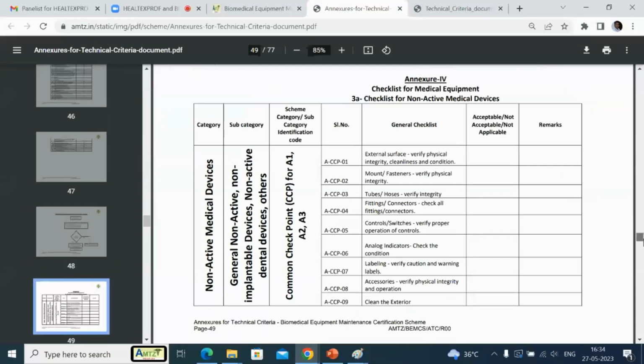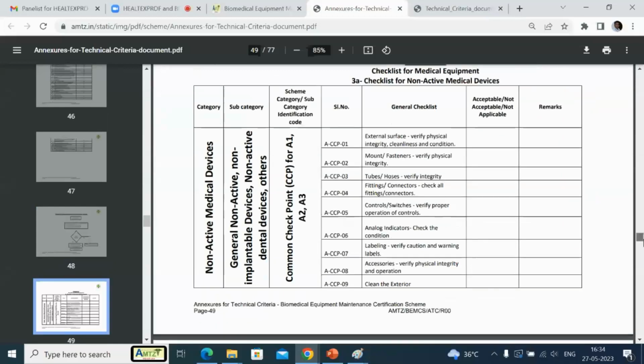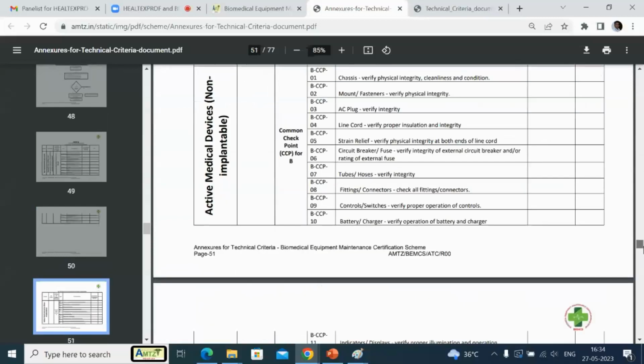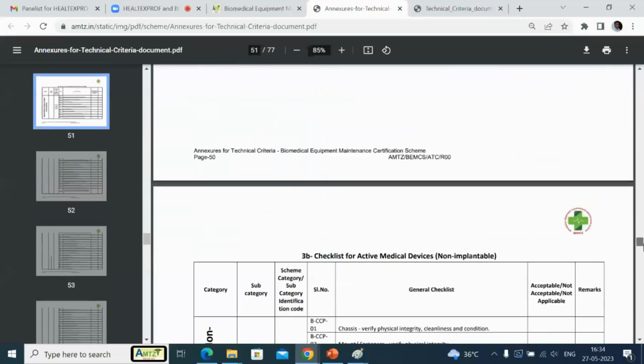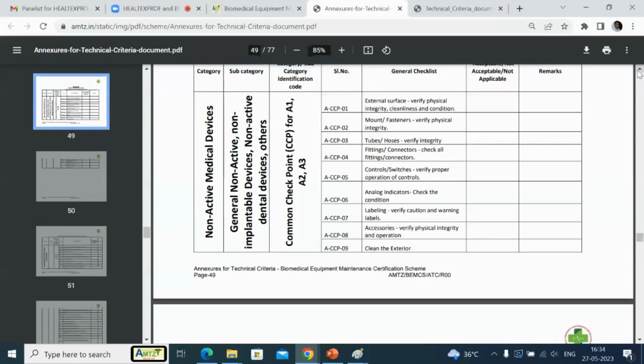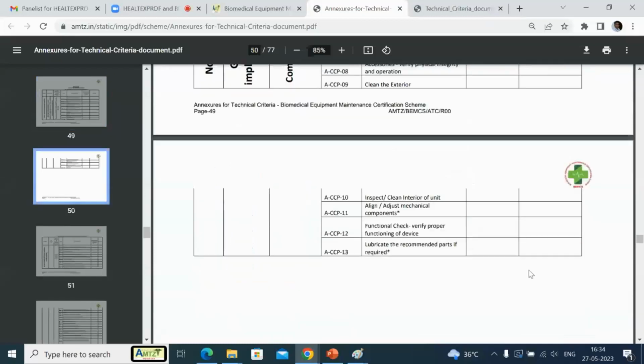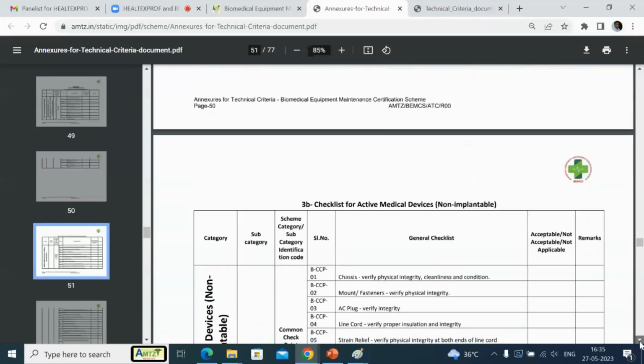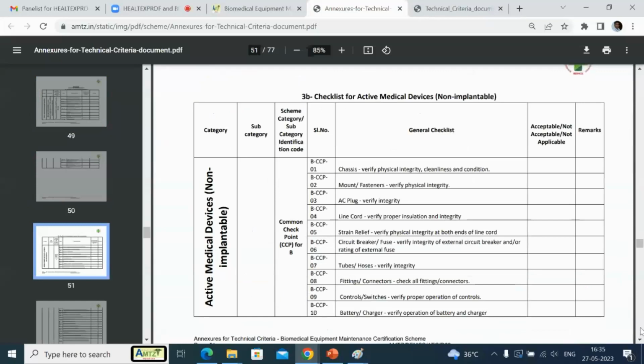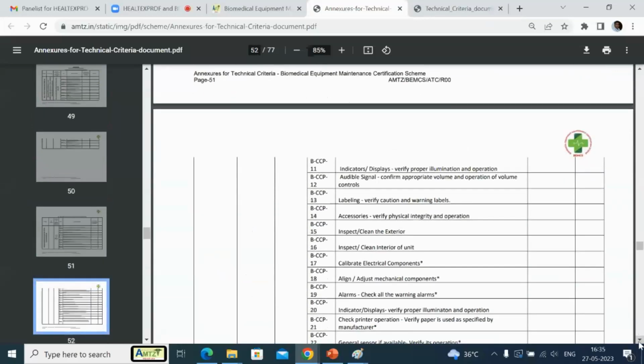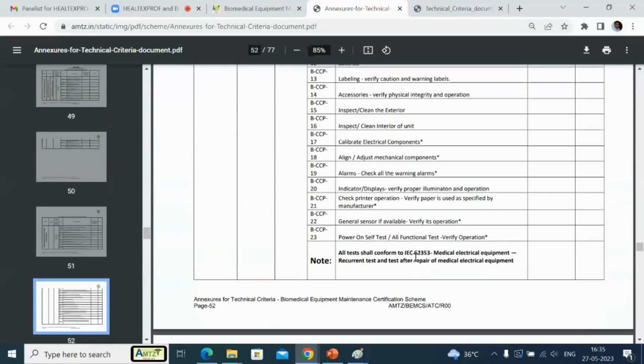These are the checklists, of which I have shown only two examples. The detailed checklist is there, so you can go through it. If you look at the first part, when it is a non-active medical device, obviously you don't have to follow IEC 62353. It is applicable only when it is an active medical device, that is, electrically powered. If it is electrically powered, then you have to make sure it conforms to the IEC 62353 standard. There is no necessity of doing it for IEC 60601-1, which is taken care of by the manufacturer. Once after installation, the minimum requirement is this.